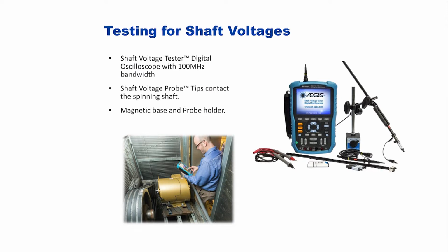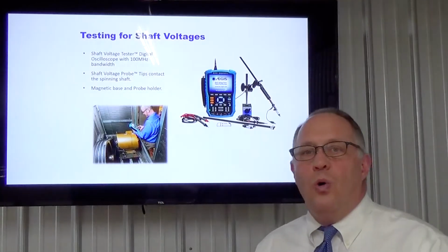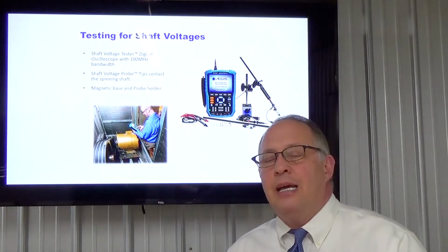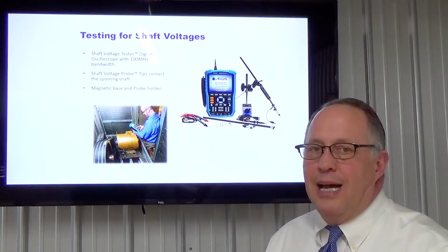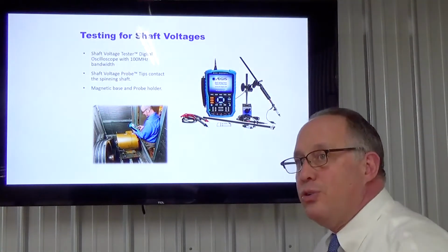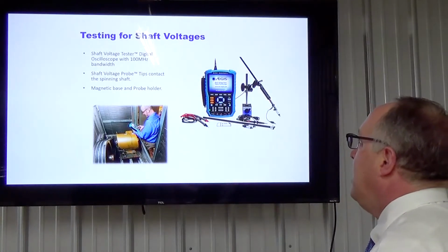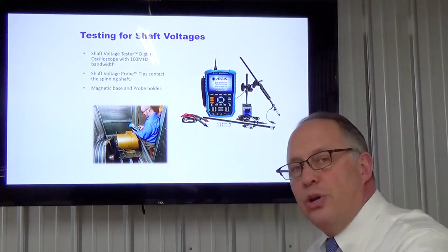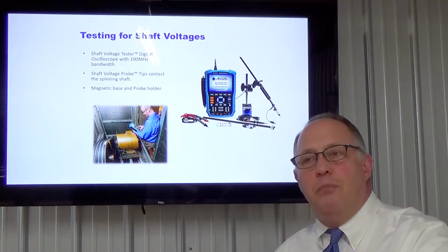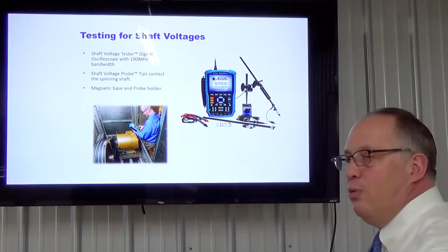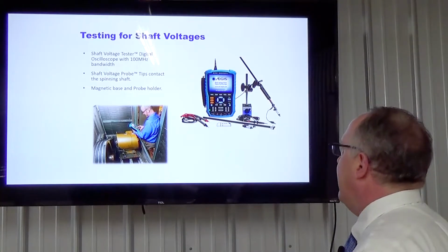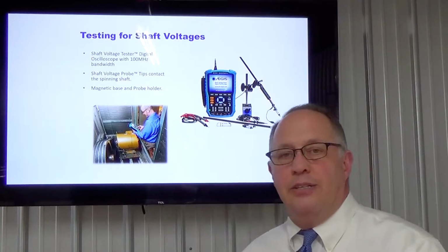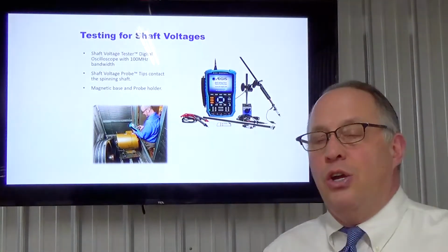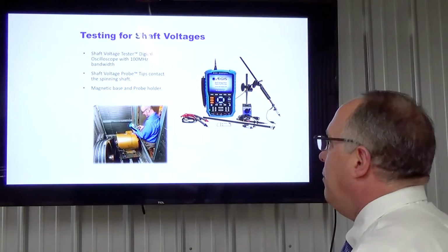How do you test for the shaft voltage? If you have a shaft voltage tester, essentially a digital oscilloscope with up to 100 megahertz bandwidth, or a good meter that has some oscilloscope-type characteristics, then you can measure these shaft voltages. You need something with a tip, a contact that you can put onto the shaft itself, and you need wiring back to a ground to be able to test that. And obviously you need something to hold that in place, because you've got rotating machinery. You don't want to be doing that where there's a possibility of damage.